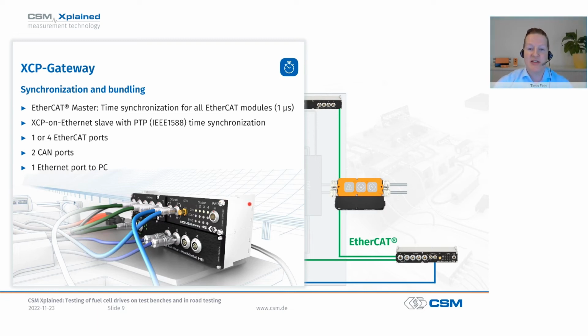This XCP gateway is a data concentrator that on the one hand collects the data of all connected fast EtherCAT measurement modules. It has up to 4 EtherCAT connections for this purpose. And in addition, it also collects all measurement data from the CAN bus connected measurement modules. Now our XCP gateway synchronizes all data streams with better than 1 microsecond jitter and then forwards the measurement data via XCP on Ethernet to the measurement computer or data logger. And for synchronous networking with other fast measurement technology, the XCP gateway is also equipped with PTP. We will come back to this later.